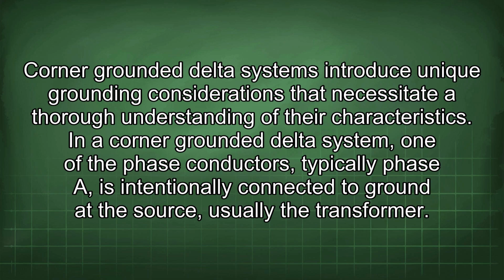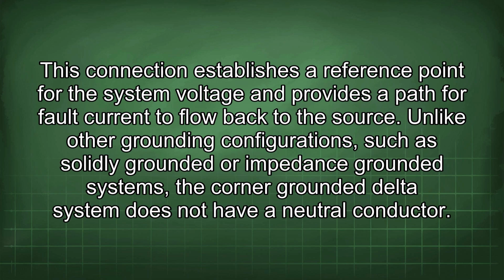Corner-grounded delta systems introduce unique grounding considerations that necessitate a thorough understanding of their characteristics. In a corner-grounded delta system, one of the phase conductors, typically phase A, is intentionally connected to ground at the source, usually the transformer. This connection establishes a reference point for the system voltage and provides a path for fault current to flow back to the source.